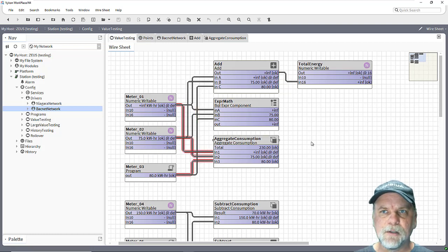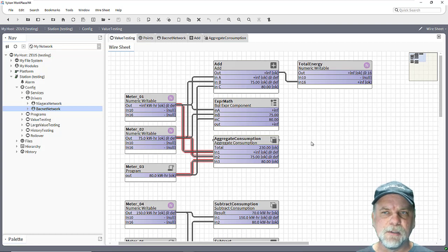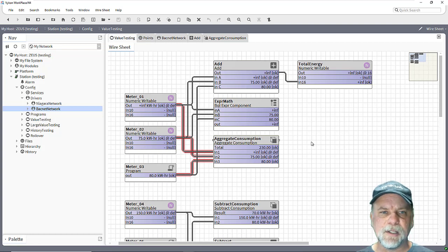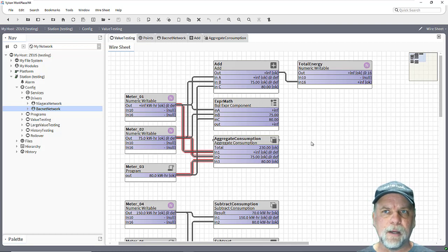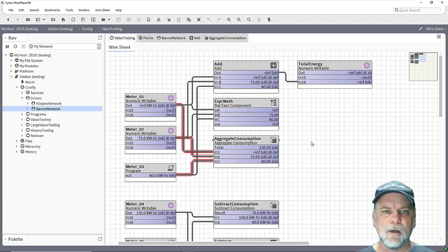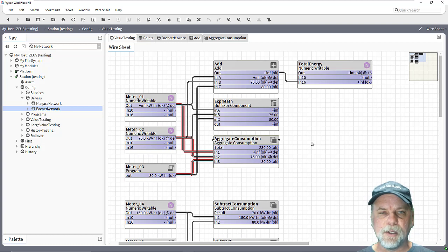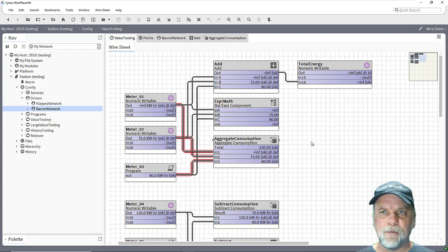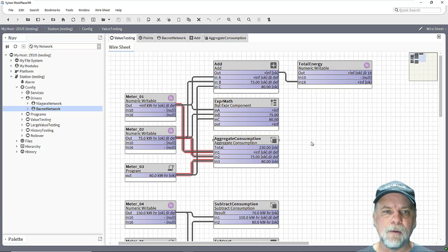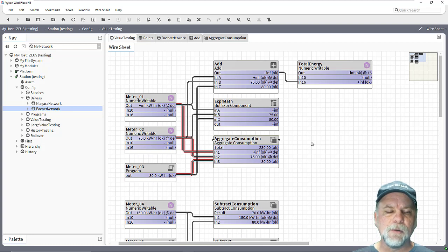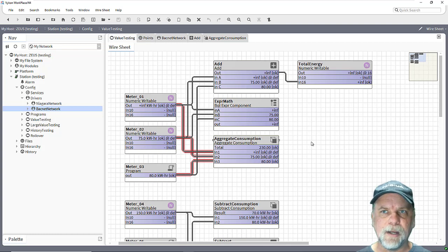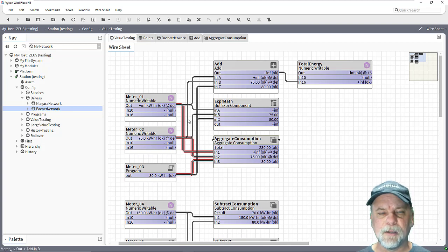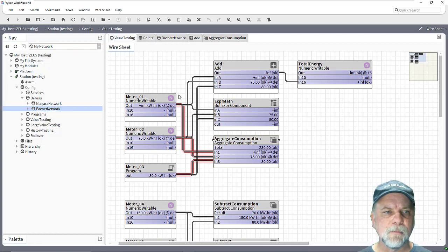So these are all things to consider as far as invalid statuses like stale, disabled, fault, or down which could impact the downstream control logic and cause those inputs to be ignored, or invalid values like perhaps NaN or positive or negative infinity. You really need to consider this in your control logic and your history collection, particularly when you're aggregating values like this where we would expect the numbers to be maintained.